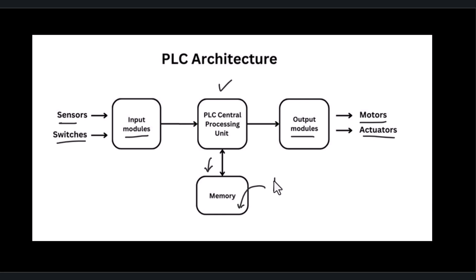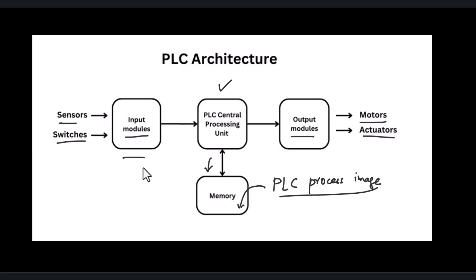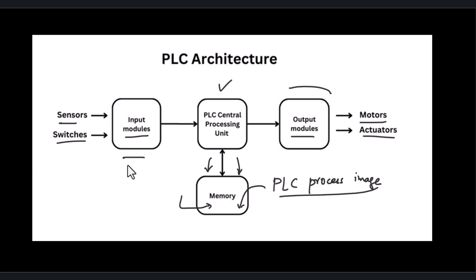In the memory, the PLC process image stores the status of all the input data coming from the input modules and the data that has to go to the output modules. The data of the program is also stored in memory, which we refer to as internal memory, because in the PLC program we have timers, counters, and memory bits in memory bytes.